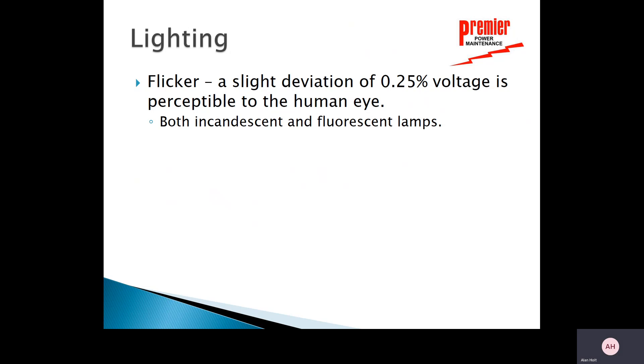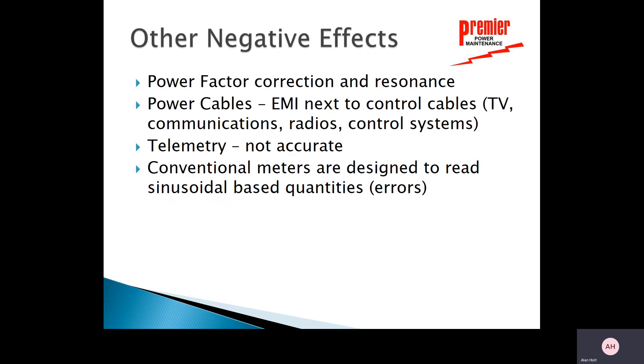In lighting, a voltage deviation of even 0.25% — similar to the total harmonic distortion in voltage — is perceptible to the human eye. This applies not just to incandescent bulbs but to fluorescent bulbs as well. You can see those fluctuations. You may not damage the light or fixture, but you might see the variation. Other negative effects of harmonics include power factor correction issues and electromagnetic interference.